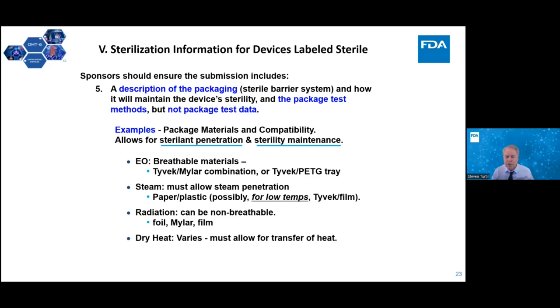And I've only seen a few failures in my experience. I think sometimes when failures occur, the manufacturer starts from zero, they start all over again, and they redesign the package. But the failures I've seen have been based on interaction of some component with the package, causing breach of sterile barrier system, or something almost as bad, something that's worse than a cosmetic change.